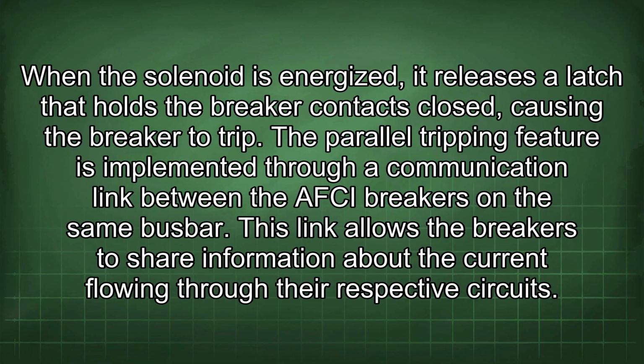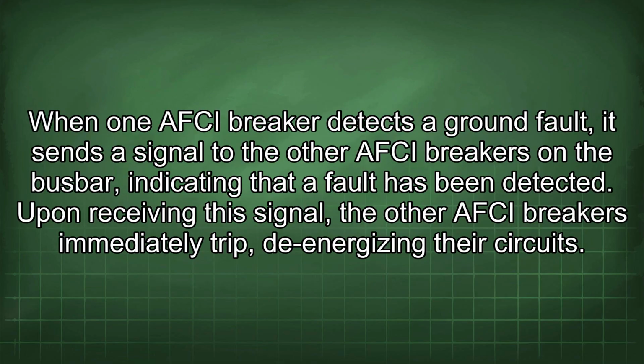The parallel tripping feature is implemented through a communication link between the AFCI breakers on the same busbar. This link allows the breakers to share information about the current flowing through their respective circuits. When one AFCI breaker detects a ground fault, it sends a signal to the other AFCI breakers on the busbar indicating that a fault has been detected. Upon receiving this signal, the other AFCI breakers immediately trip, de-energizing their circuits.